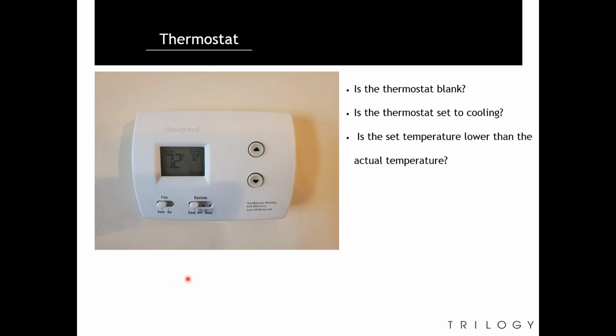If the thermostat is on and it's set to cooling and it's still not coming on, go ahead and take the batteries out if they have batteries in them and plug it back in to see if the thermostat comes on. If it goes off, we have something that's wrong on the inside. We do not have power to the thermostat itself.